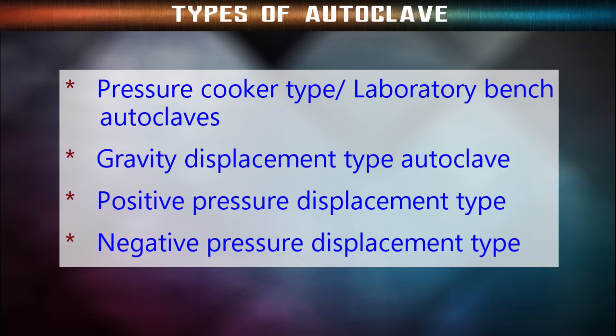Next is the positive pressure displacement type. In this type of autoclave, the steam is generated in a separate steam generator, which is then passed into the autoclave. The autoclave is faster as the steam can be generated within seconds. This type of autoclave is an improvement over the gravity displacement type.